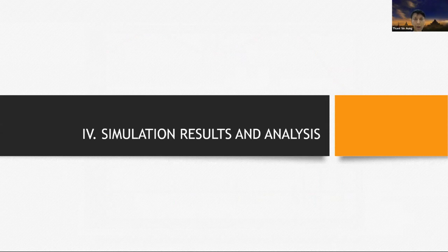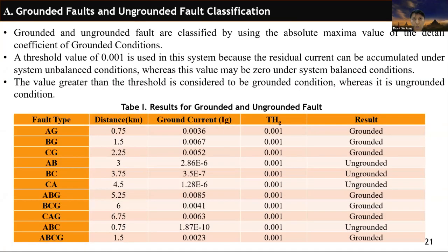Grounded and ungrounded faults are classified by using the absolute maximum values of the detail coefficients of the grounded condition. A threshold value of 0.001 is used in the system because residual current can accumulate under a system unbalanced condition. Whereas this value may be 0 under a system balance condition, a value greater than the threshold is considered a grounded condition, otherwise it is an ungrounded condition.